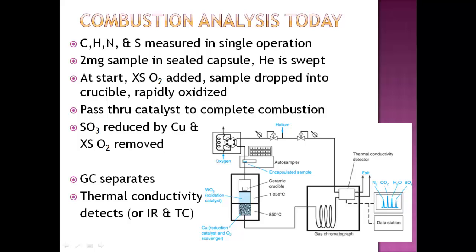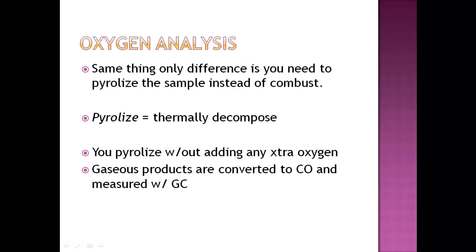One thing that you have to know is that chromatographic separation requires that the entire sample be injected at once. You can't inject part by part of the sample, because the whole point of GC is to separate a mixture into its components. So if you inject things little by little, when you read your data, it's going to be wrong, because you have to inject everything at the same time so that the actual instrument can separate it for you. So that was separating, at one time, carbon, hydrogen, nitrogen, and sulfur.